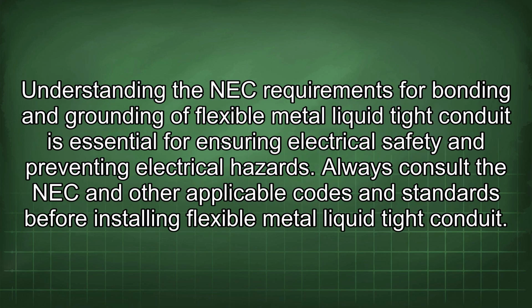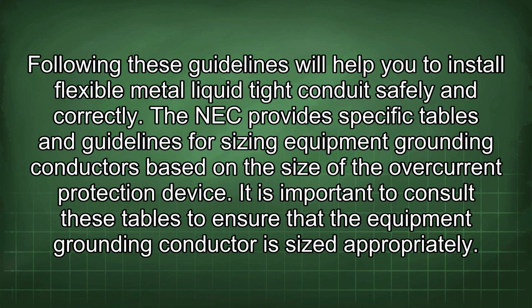hazards. Understanding the NEC requirements for bonding and grounding of flexible metal liquid tight conduit is essential for ensuring electrical safety and preventing electrical hazards. Always consult the NEC and other applicable codes and standards before installing flexible metal liquid tight conduit. Following these guidelines will help you to install it safely and correctly. The NEC provides specific tables and guidelines for sizing equipment grounding conductors based on the size of the overcurrent protection device. It is important to consult these tables to ensure that the equipment grounding conductor is sized appropriately.